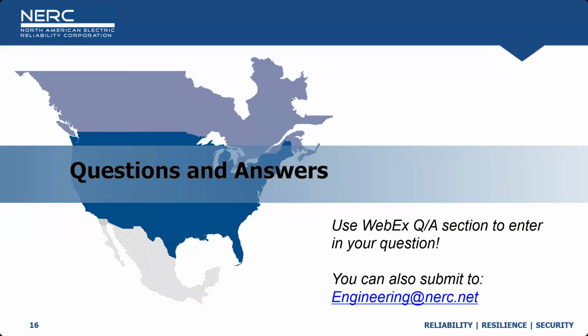As we look at the recommendations out there across the alert, the various white papers, and now the draft reliability guideline, a lot of this hinges on what the potential stability risks are based on customer-initiated load reductions that might occur rapidly. Is the main focus here to ensure transient stability or system stability? We do recognize that if an entity requires ride-through for a specific type of load, or all loads, it could be difficult or impossible for some types of loads to meet that.